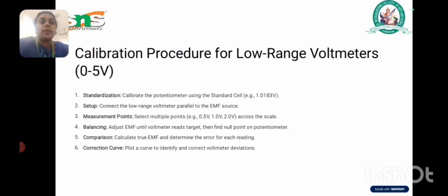Next, the calibration procedure for low range voltmeters, 0 to 5 volts, using some batteries: standardization, setup, measurement points, balancing, comparison, and correction graph.